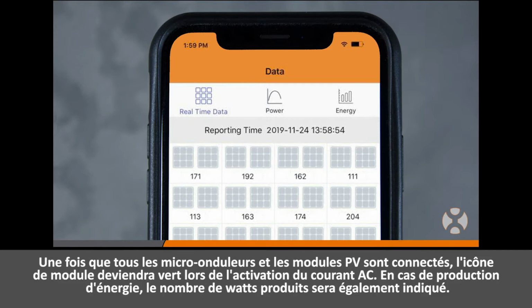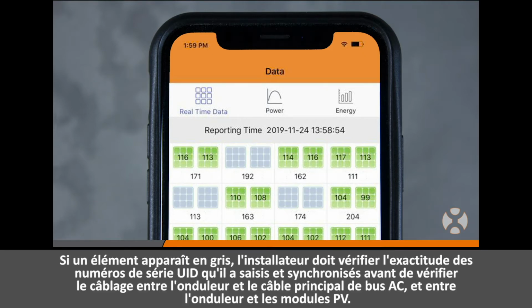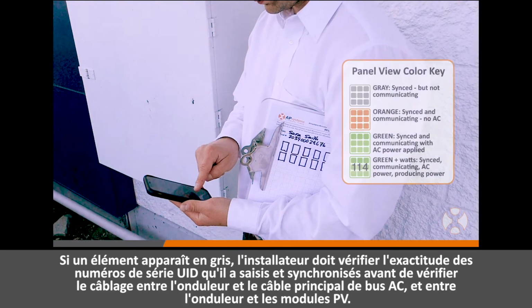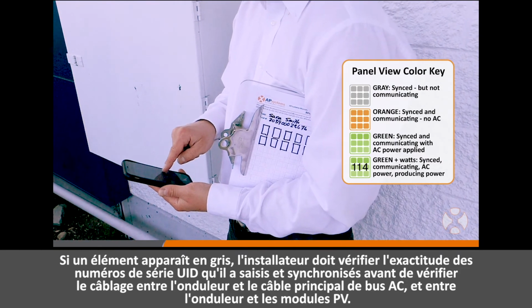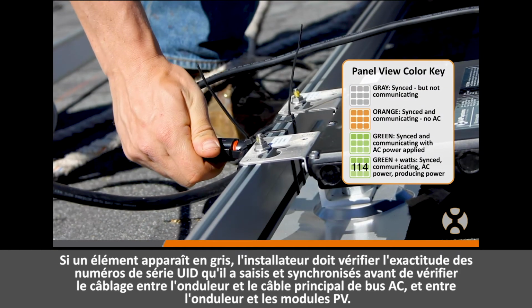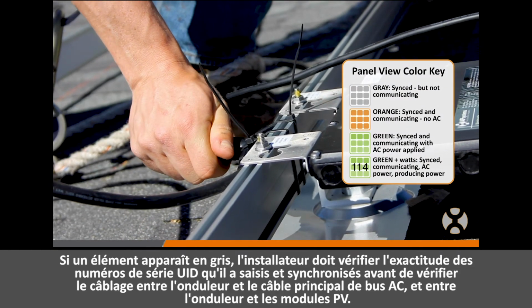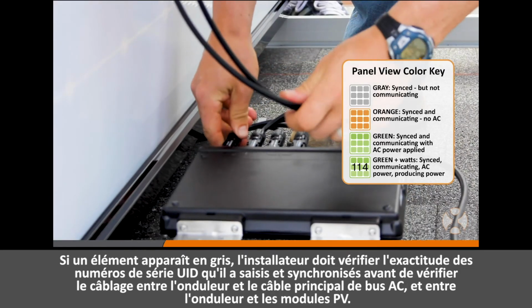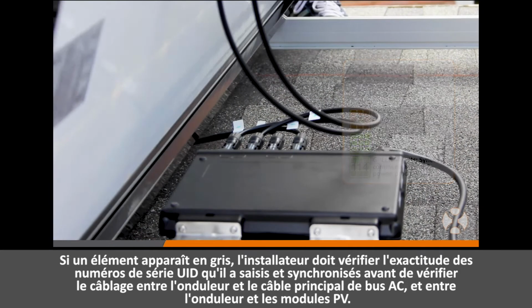Once all the PV modules and microinverters are connected, the module icon will turn green when AC power is applied, and will display a wattage when they are producing power. If any display is gray, the installer should check the UID serial numbers they entered and synced for accuracy before checking cabling connections between the inverter and the AC bus trunk cable and between the inverter and the PV modules.